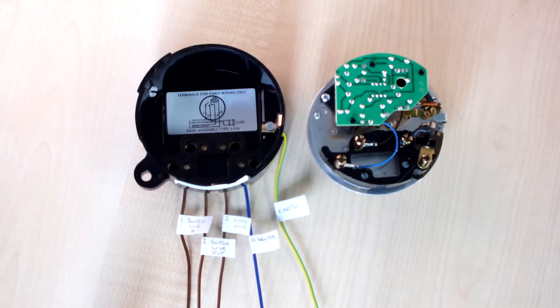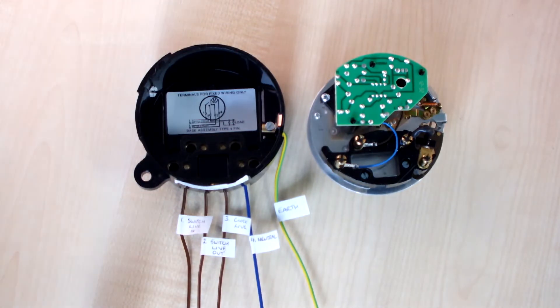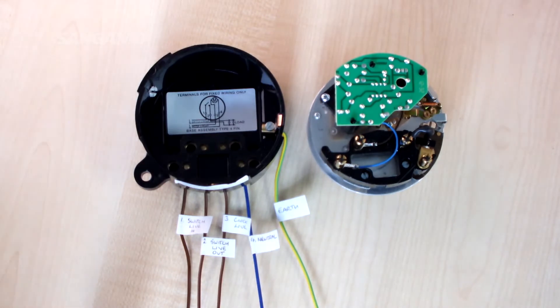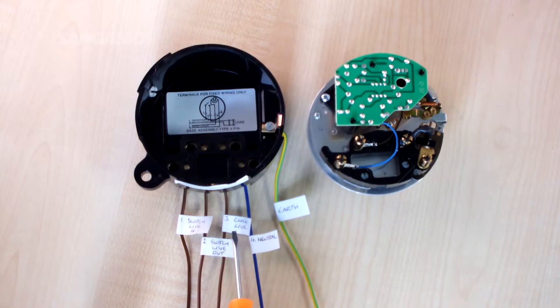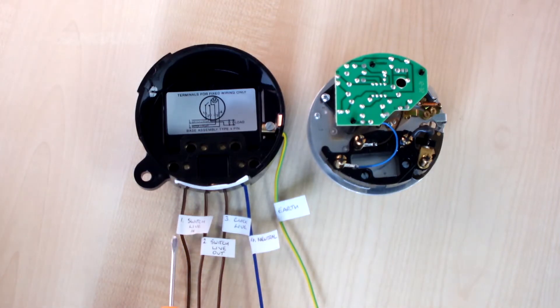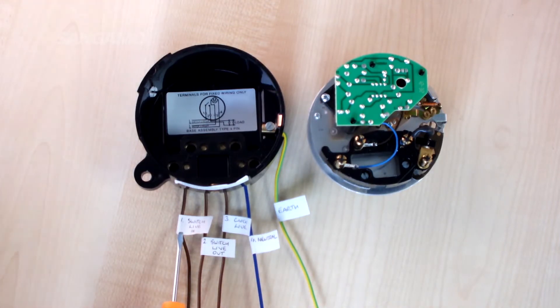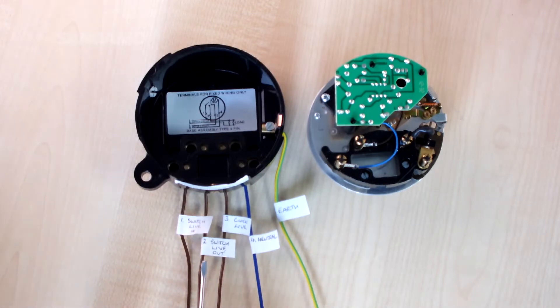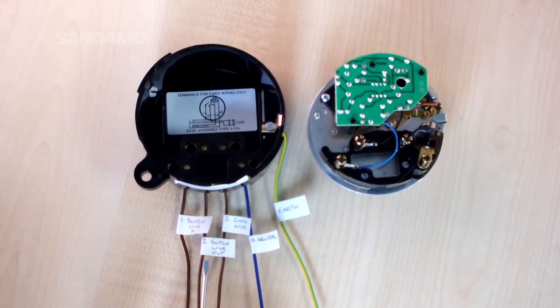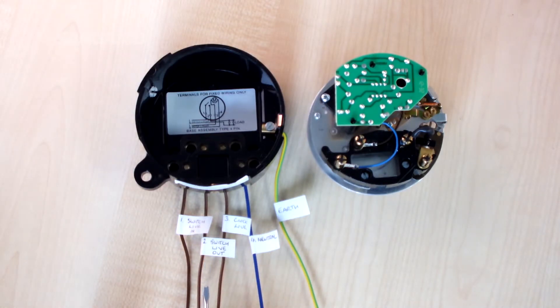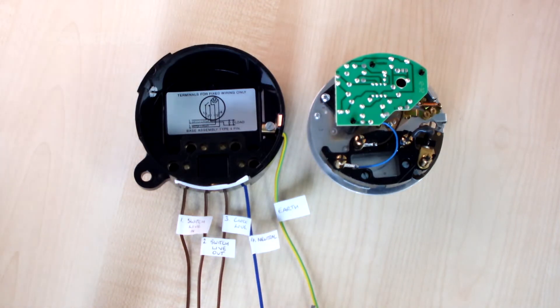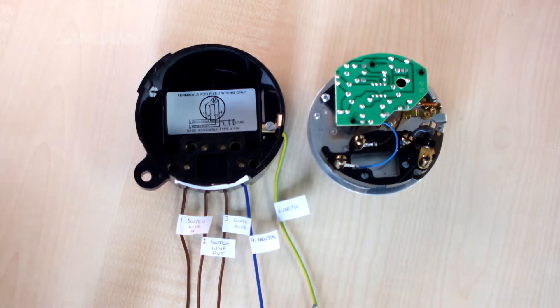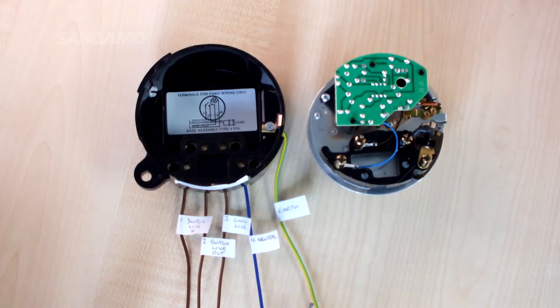So in terms of the actual wiring of it, terminal 3 is your live in to the clock, terminal 1 is a live in for the switching circuit, terminal 2 is your live out to your load, terminal 4 is for neutrals, and you've got the essential earth into the side of the unit.